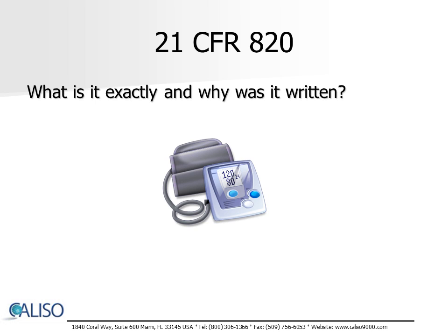Current Good Manufacturing Practice Requirements, also known as CGMP, are set forth in this regulation. The requirements are specifically intended to ensure that finished medical devices will be safe and effective and in compliance with FDA requirements. 21 CFR 820 is the United States regulation equivalent to the European standard ISO 13485-2003, in that they are both written specifically to dictate or set forth the requirements by which a medical device is designed, developed, manufactured, and monitored.